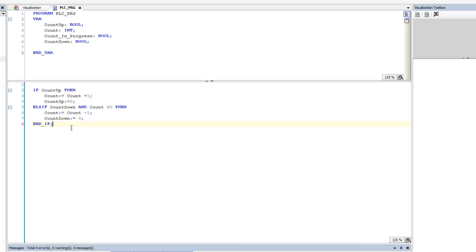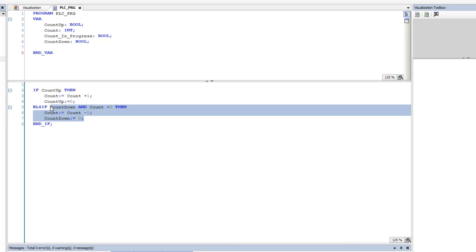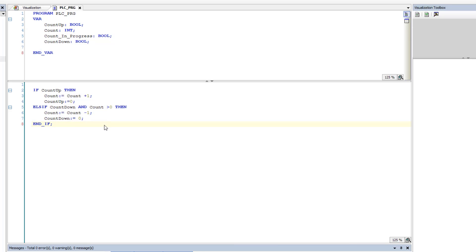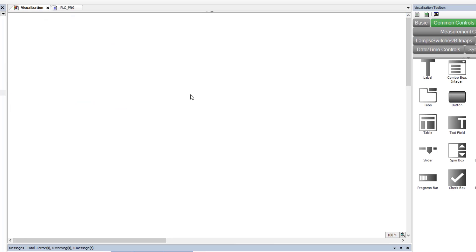It's really a simple process. If count_up happens, we take count plus one and then turn the count button off so it only counts one time — it's like a one-shot without having a one-shot instruction. And else if count_down happens, if count is above zero, then we enable the ability to subtract.